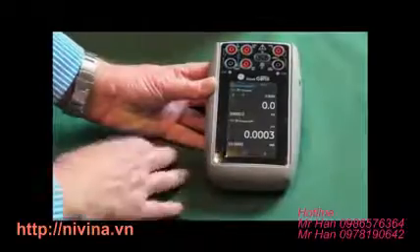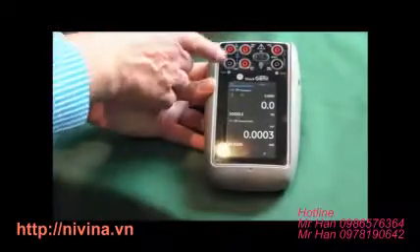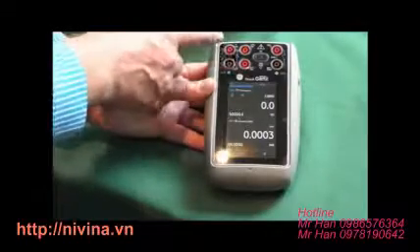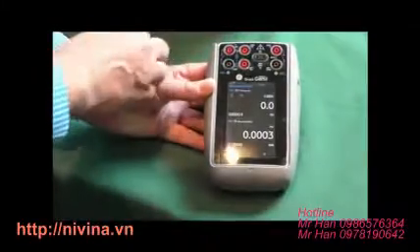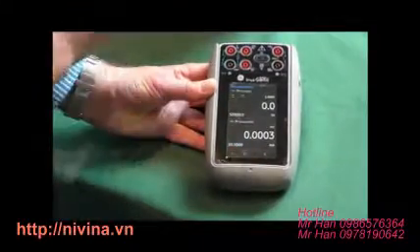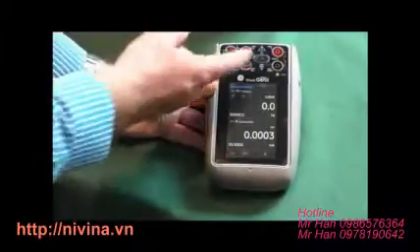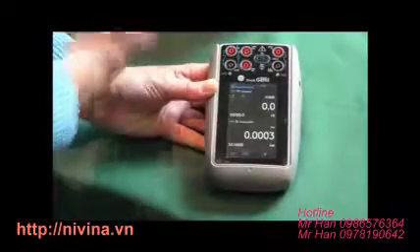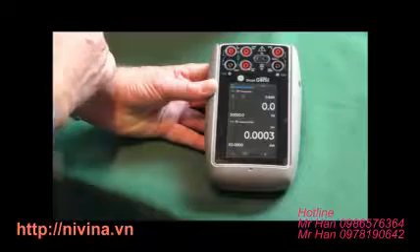On channel 1, as you can see, we've got some graphics on there indicating what we can do. We can source or measure a full 4-wire RTD, and it will test all the compensation lines on there. We have our thermocouple connection here, and over on this side we have a milliamp and a 24-volt power supply.